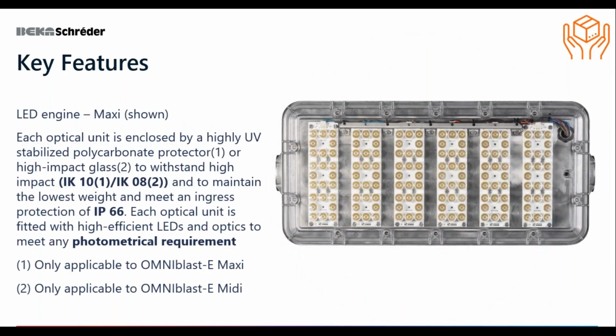Another key feature with regards to the Maxi product, it comes in two options with regards to protector: a polycarbonate protector at a higher IK rating of 10, and also the high impact glass, obviously with a slightly lower IK rating of 08. And we really try and optimize this with regards to the weight of the product and driving the ingress protection as optimal as possible at IP66. And this really gives us a chance to protect the optical unit that is fitted with these high efficient and high power LEDs, because we really want to make sure that the photometry requirement and what is coming out of this unit is really protected.